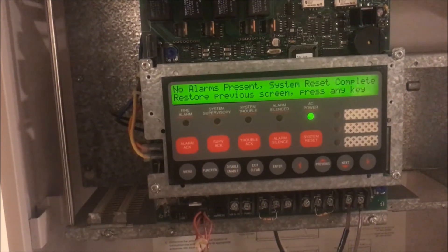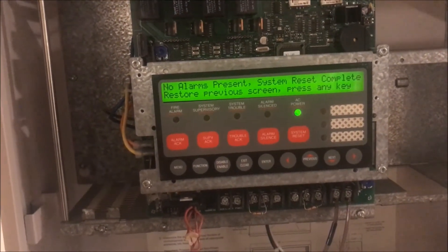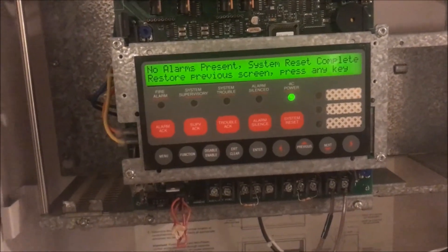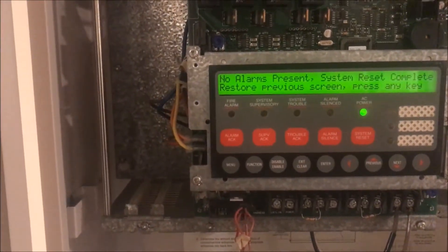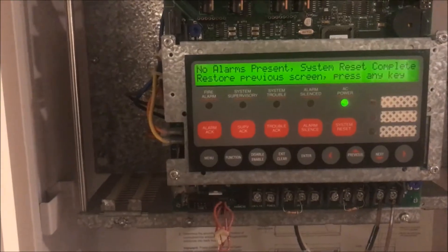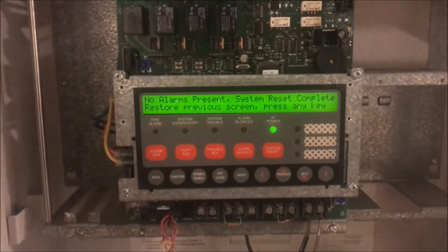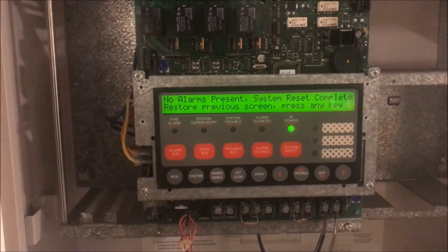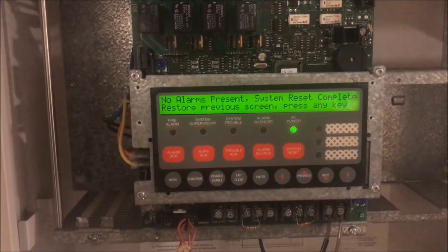This has been going on for six minutes now. I've been trying to reset it and it was unhappy about the smoke detector head — kept saying 'wrong type' and that it was still in alarm. And look at that, it's doing everything it's supposed to. That moment when your panel won't reset — yeah, it's kind of stressful.